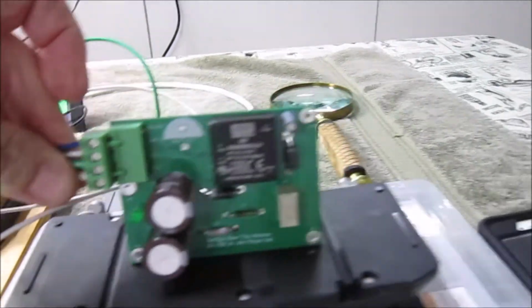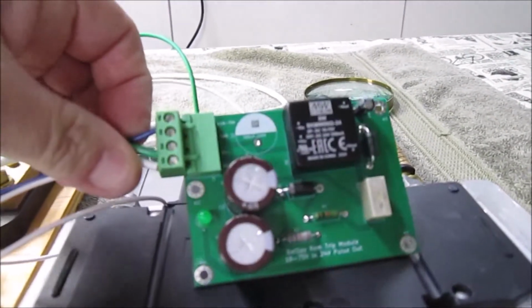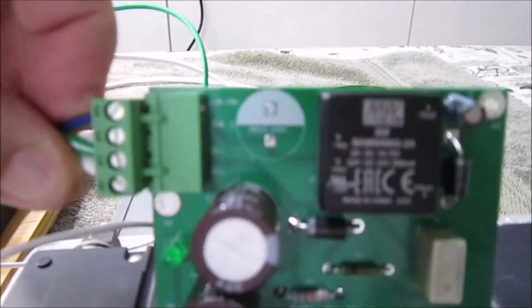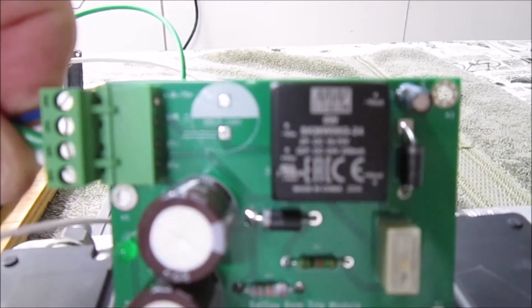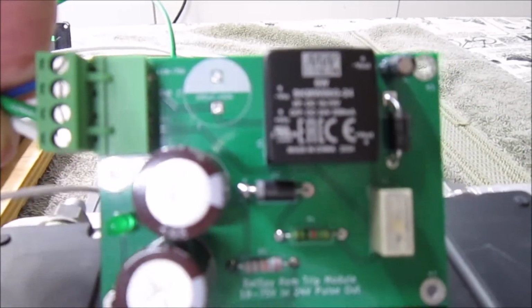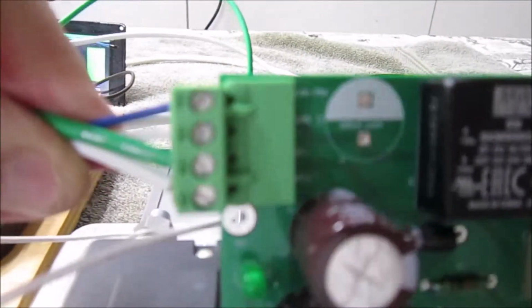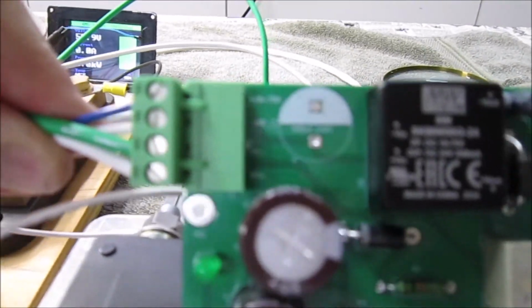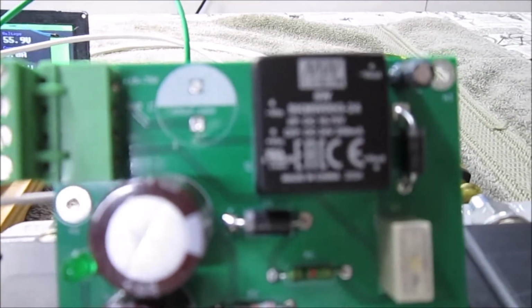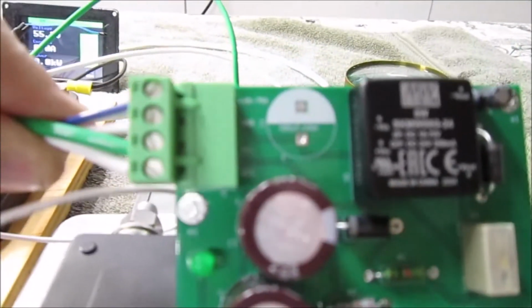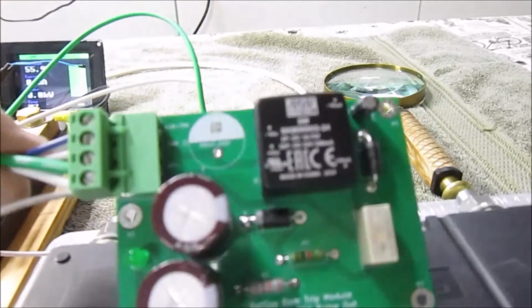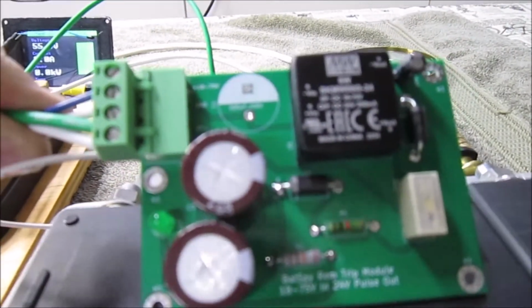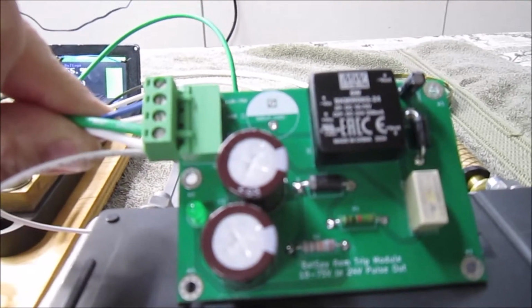So my solution is a circuit board. It's actually pretty simple. It's all analog. I've got a regulated power supply, 24 volts. Coming power from the BMS would come in between 18 and 75 volts. It regulates it down to 24, charges these capacitors, and then if the BMS releases, this relay is triggered and the power from the caps dumps into the remote trip coil and it shuts off.